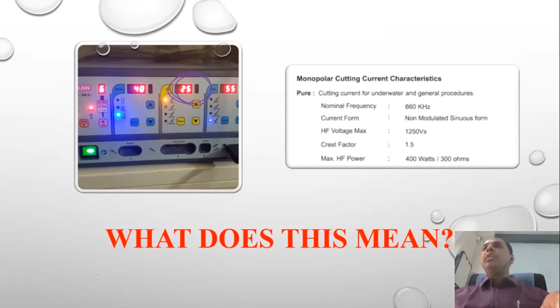If I set the watt at 25 in pure cut mode, the ESU will adjust the voltage such that it delivers a maximum output of 25 watt only. If suddenly the electrode encounters high tissue impedance, the machine will increase the voltage as per its algorithm. This may or may not be beneficial in cutting the tissue, and the surgeon may have to increase the power to bring the desired effect. If the power is more than required for the tissue, it will increase collateral damage.